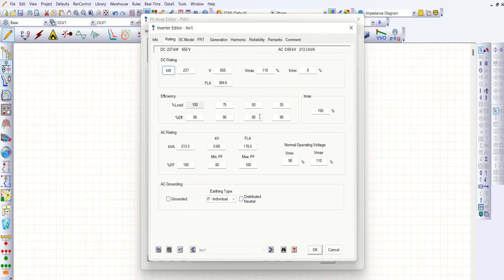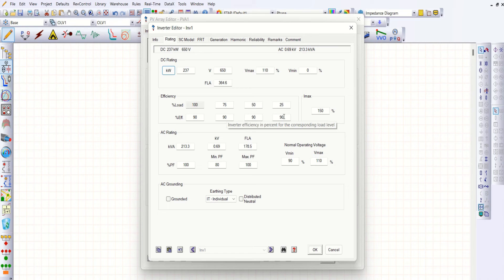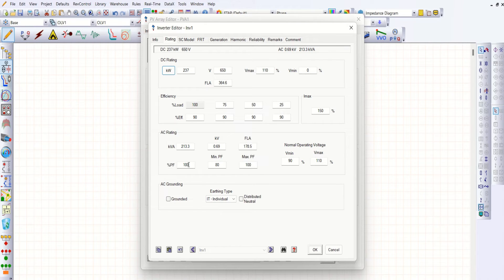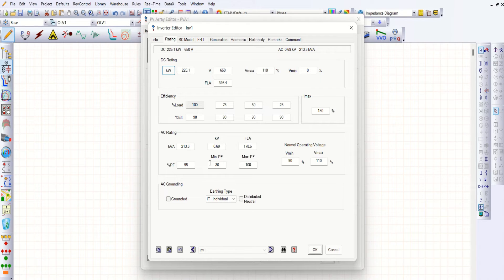The rest of the values are as-is: efficiency throughout load operation from 25% to 100% is 90 percent. Power factor is 100 percent maximum and 80 percent minimum. You can also change your rated power factor — let me fix it to 95 percent. You can see the corresponding change here as well.